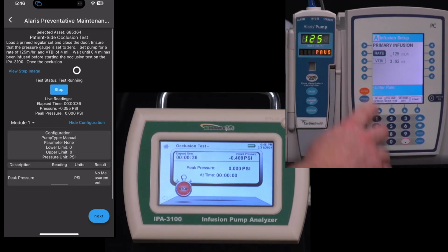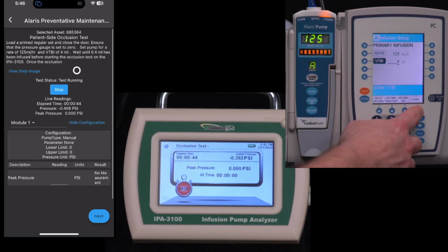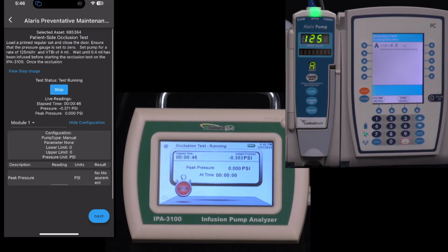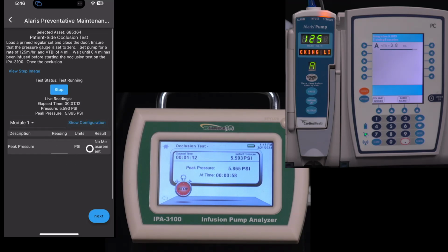Now, unfortunately, we can't communicate with the pump to send the settings, but we can tell you exactly what to do. So it's telling me to do 4 milliliters at 125 milliliters per hour. So I'll go ahead and start that, and we'll see the occlusion test is running here. Now we can also see those readings shown on MyBC Mobile. So it's communicating with the IPA 3100, it's getting those values and showing that on the screen. And we can hide the configuration just to show our test results.